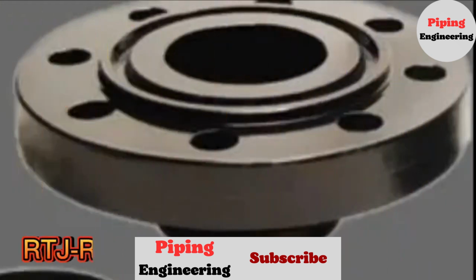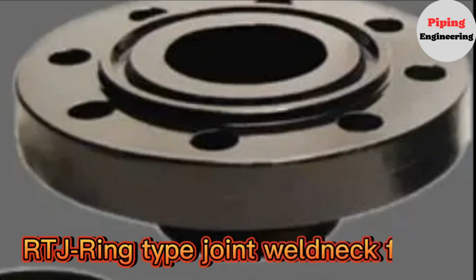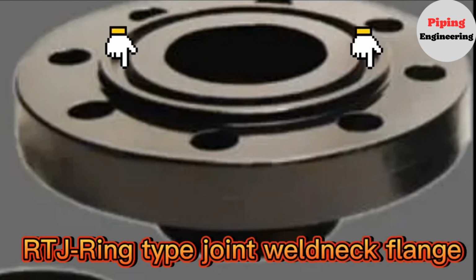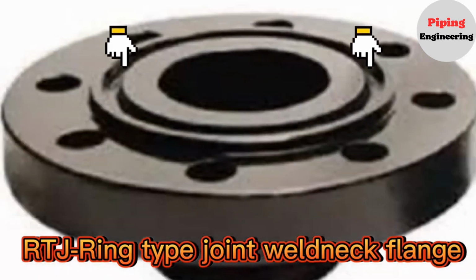What is the RTJ, ring-type joint, weld neck flange? An RTJ flange or ring-type joint flange is one of the various types of flanges used widely in piping and pipeline industries. A ring-type joint flange, RTJ, is a machined metallic flange with a deep groove cut into its face. In this groove rests a metal ring which gets compressed when the connecting bolts of the flange are tightened.